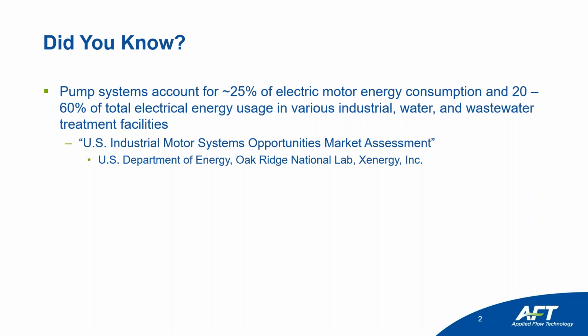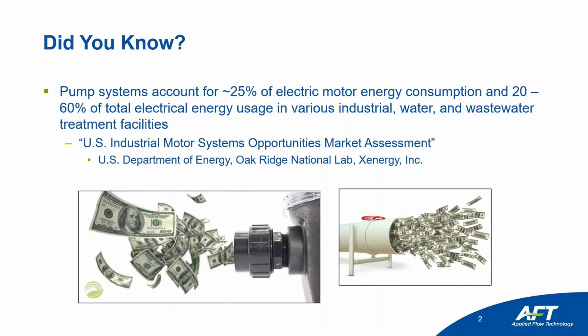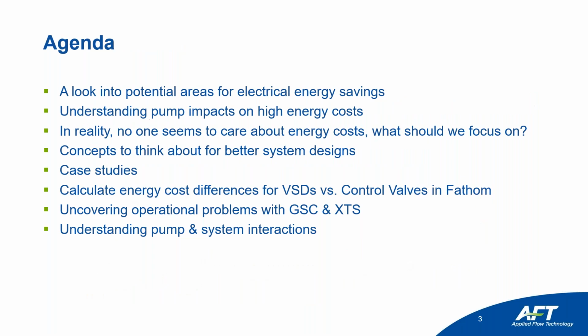Well, same thing here. If you're throttling that flow, that's going to cause the pump to operate away from its sweet spot. And not only are you wasting energy, but you're also going to cause a lot of other problems, vibrational issues. It's going to increase your seal failure rate and lots of things that you want to try and avoid. So we're going to talk about all that stuff today. Basically, you don't want to be just pumping money right out of the pipeline there. You want to try to find ways to increase your cost savings as well as eliminate those expensive repair costs.